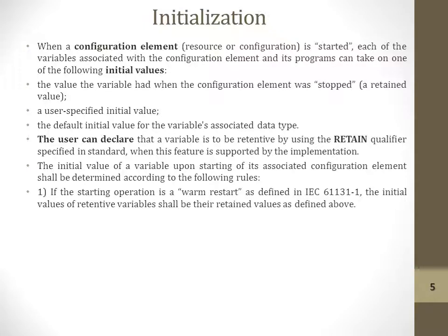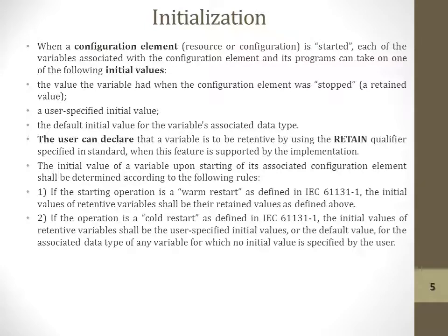First, if the starting operation is a warm restart as defined in the standard, the initial values of retentive variables shall be their retained values as defined above. Second, if the operation is a cold restart as defined in the standard, the initial values of retentive variables shall be the user-specified initial values, or the default value for the associated data type of any variable for which no initial value is specified by the user.